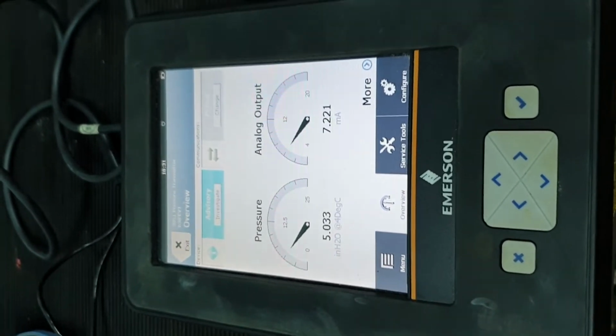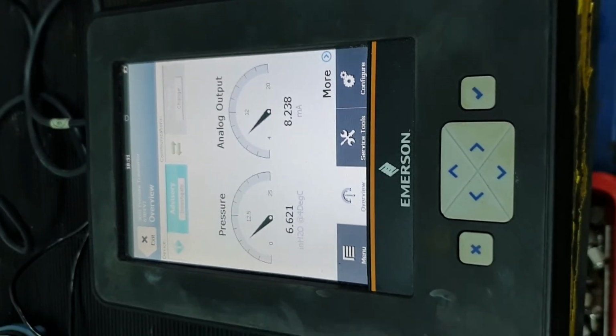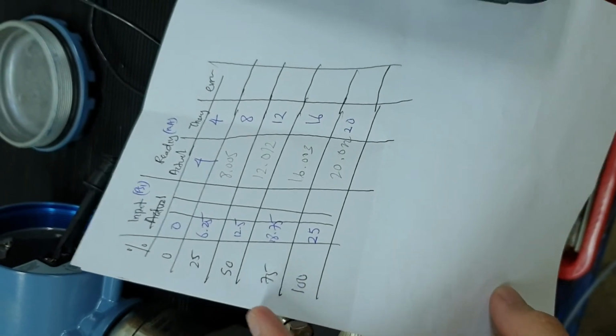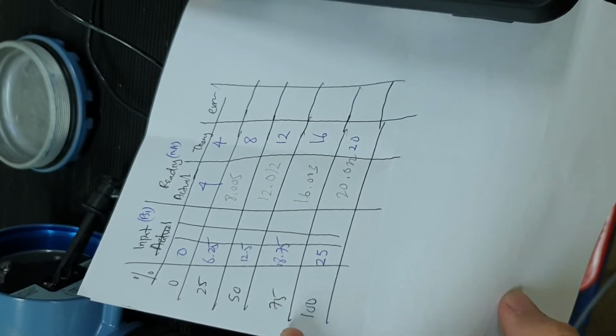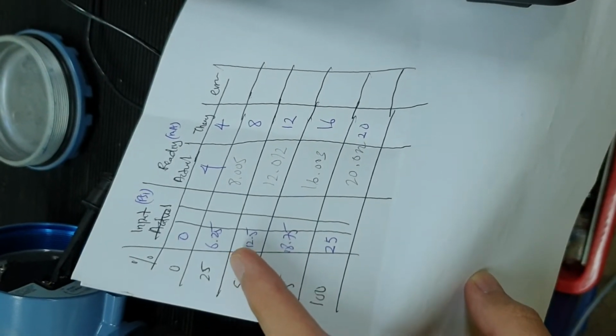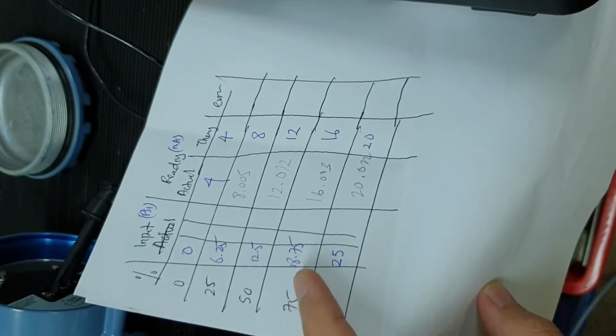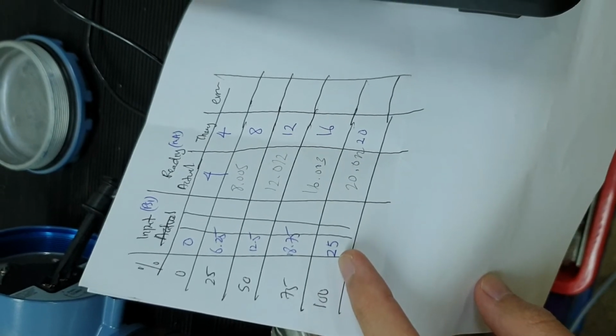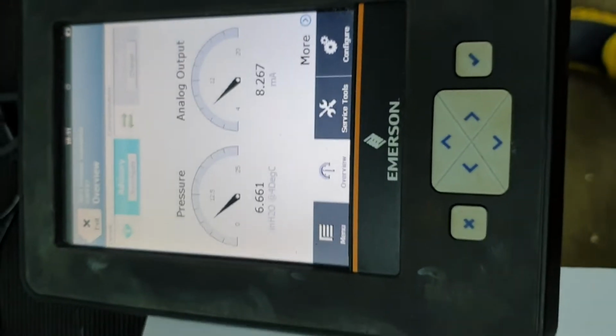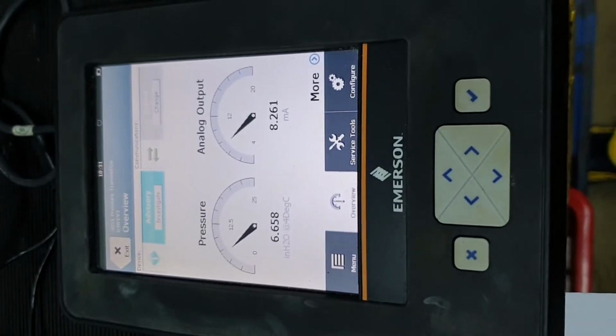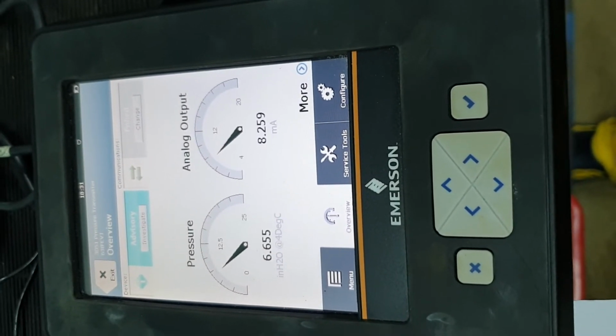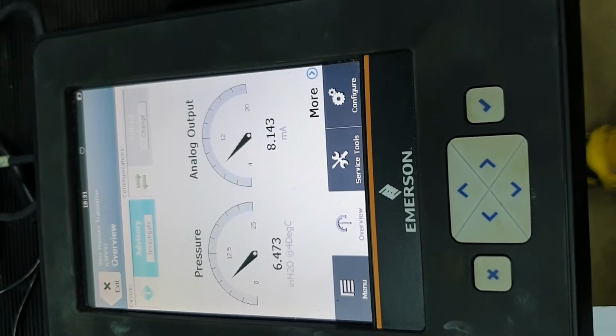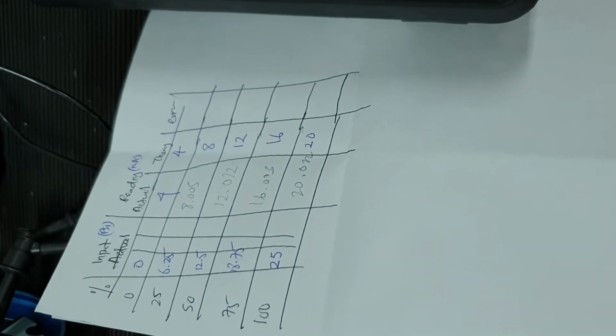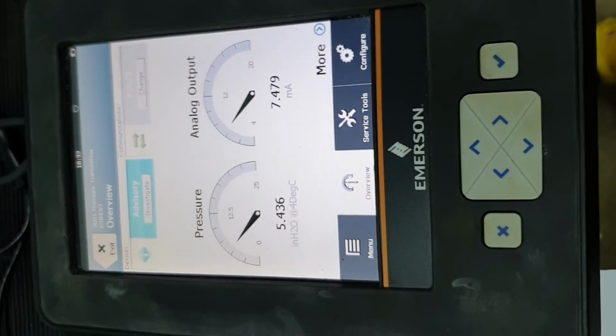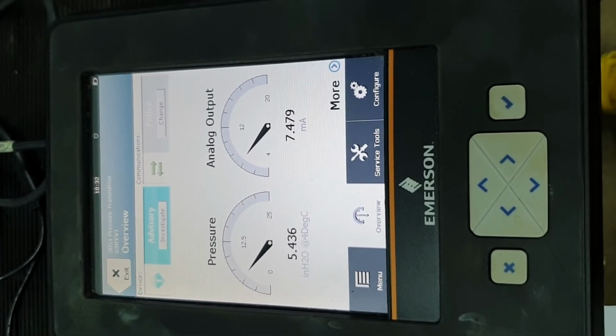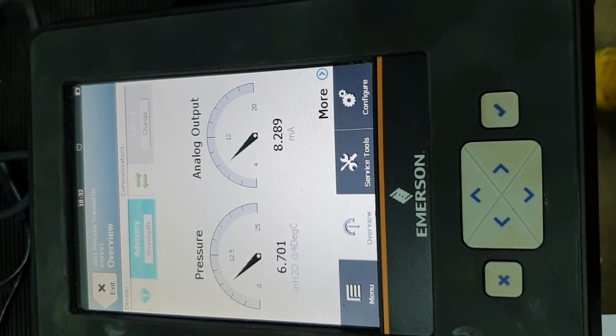As I mentioned earlier, we're going to take values from 0% up until 100% with a step of 25% each, and we are expecting to get 6.25 at 25%, 12.5 at 50%, 18.75 at 75%, and 25 at 100%. As we increase the knob at the step of 25%, which is equivalent to 6.25 inches H2O, we are going to expect a current of 8 milliamp. So 6.25 inches H2O will be equivalent to 8 milliamps.